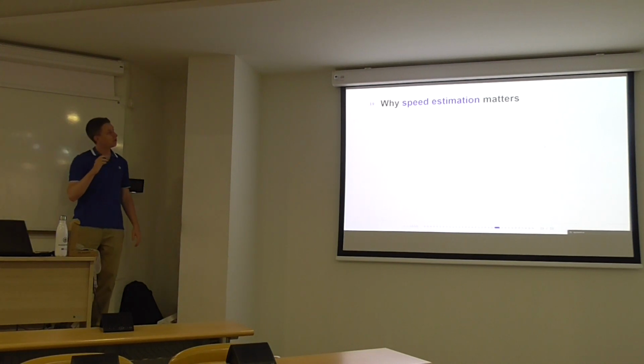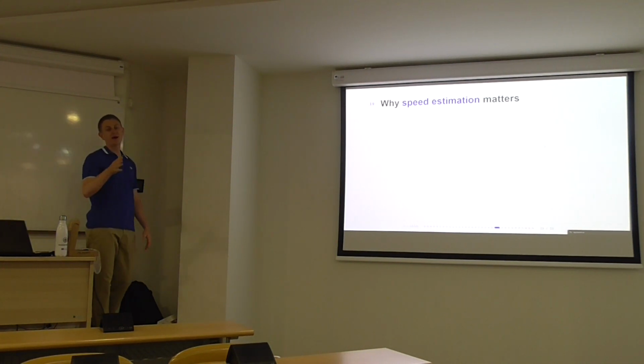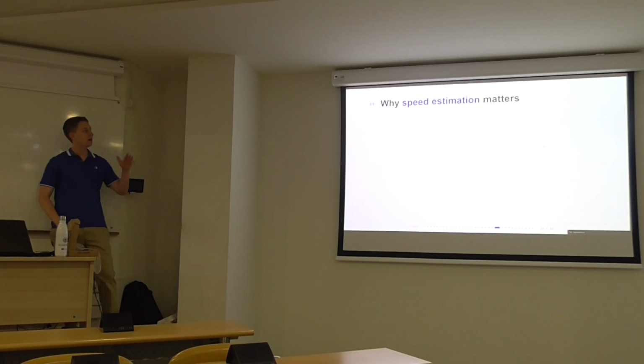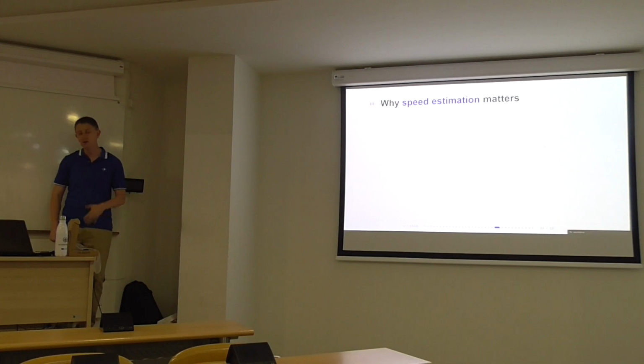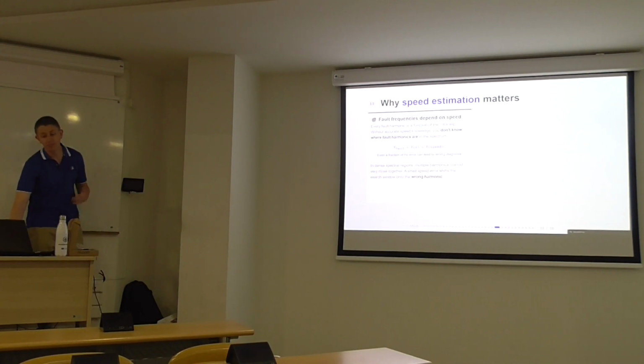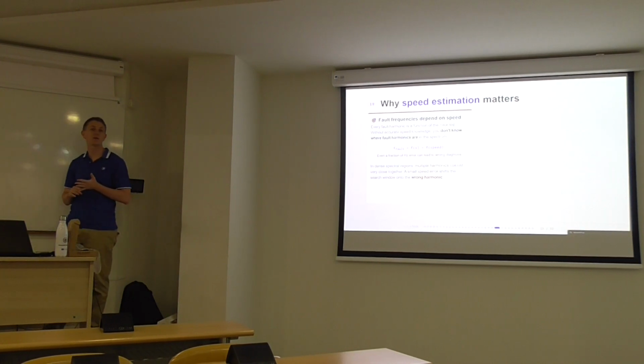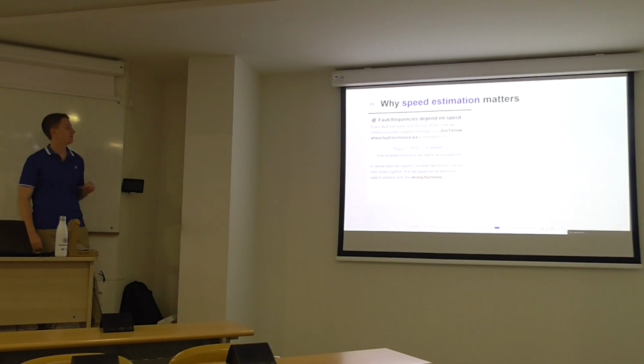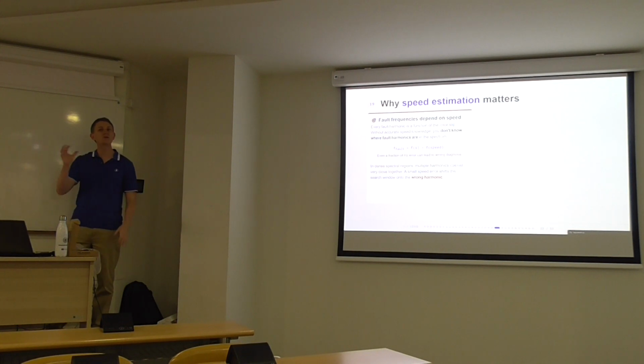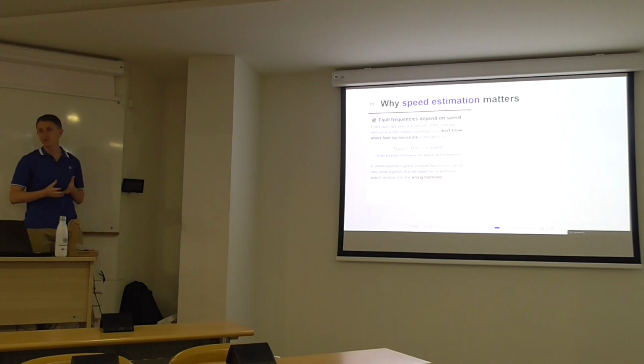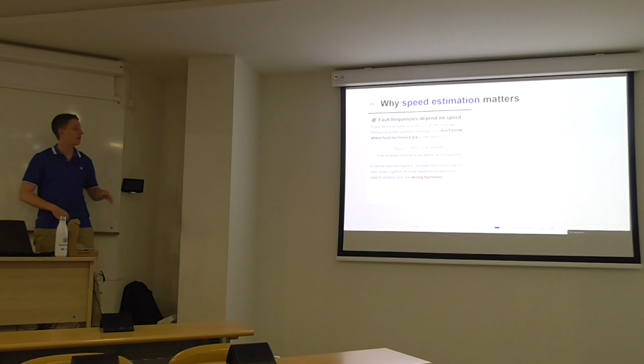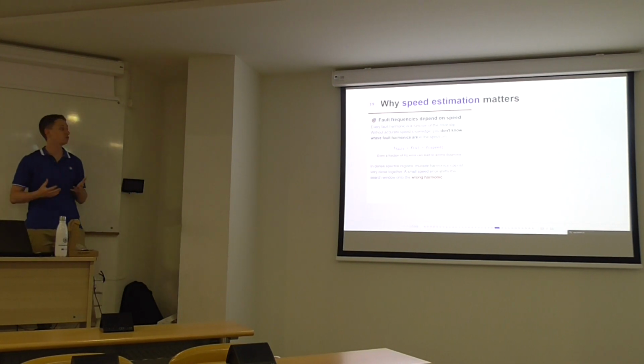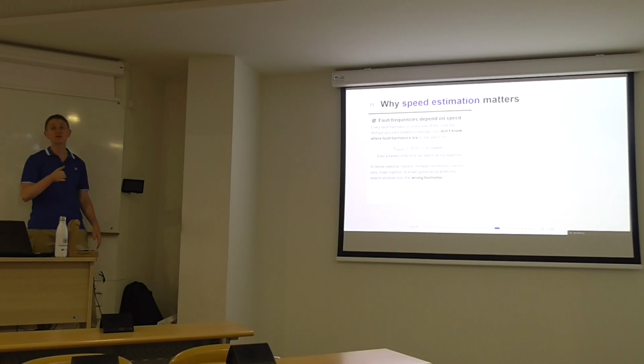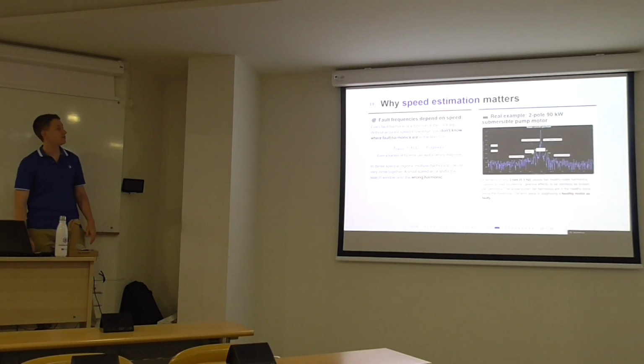And now let's go to the block of the speed estimation. Okay, so now I have told you how to acquire those low noise signals. Now let's see how to estimate the speed correctly. So once again, why does speed estimation matter? As I told you before, every fault harmonic is a function of the rotor speed. So without accurate speed knowledge, you don't know where to look in the spectrum. In dense spectral regions, as you will find in reality, in industrial environments or when the motor is fed with a variable frequency drive, multiple harmonics coexist very close together. So I need to know very precisely where to look, so that I don't confuse a healthy harmonic with a faulty one.